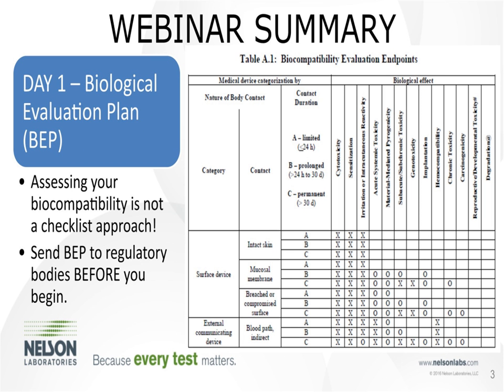For day one, Thor talked about the biological evaluation plan. A small portion of the FDA guidance document table is shown here — it helps identify the risks a device may pose to a patient. A big point is that assessing biocompatibility is not a checklist approach. It's not merely going to the table and doing every test with an X or O. It's understanding the real risk to your patient and performing the necessary tests or justifying why they're not necessary. Thor also emphasized submitting a BEP to regulatory bodies before you begin, so reviewers can identify any disconnects early.